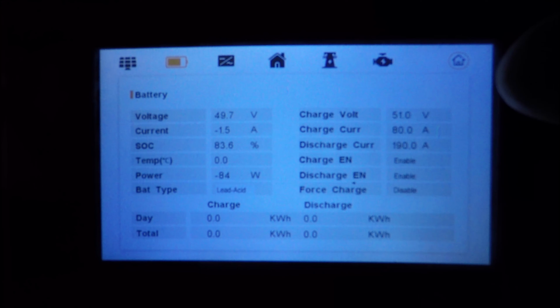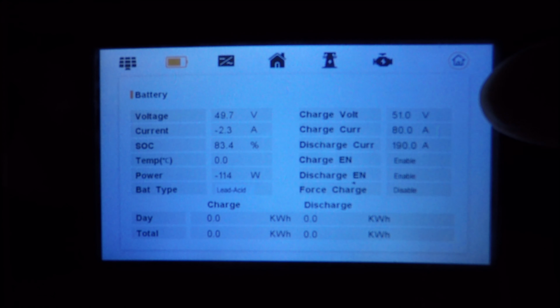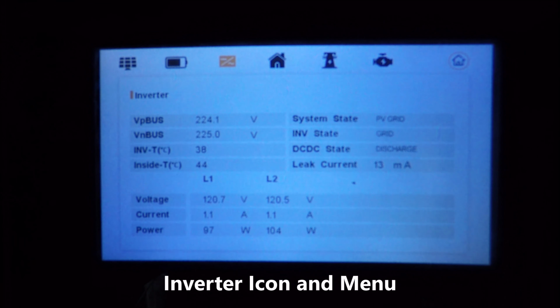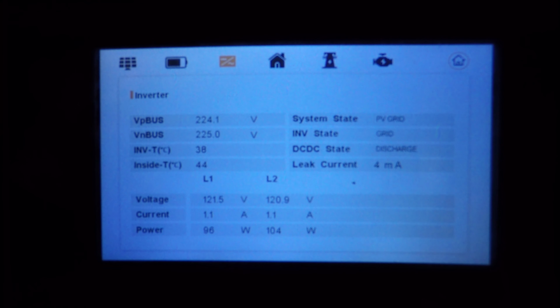We have our charge voltage, our charge current, and our discharge current. These settings are overridden by the settings in the setup menu of our total charge and discharge for the day and for the totals. You can also see the inverter state. So right now we are using PV grid. The inverter state is grid. DC to DC state is discharge because we are using battery power.